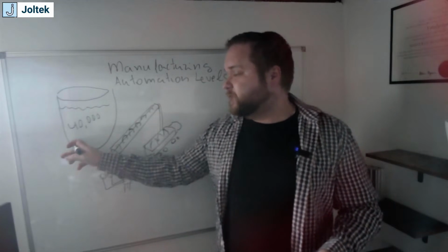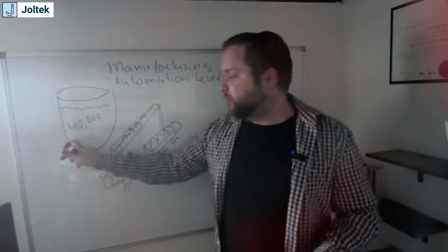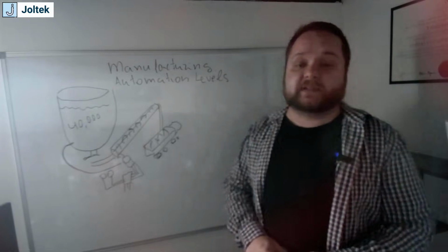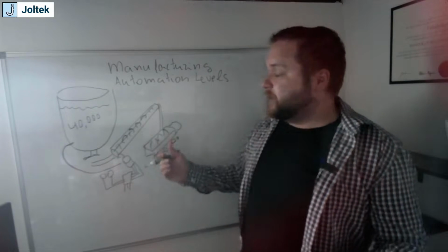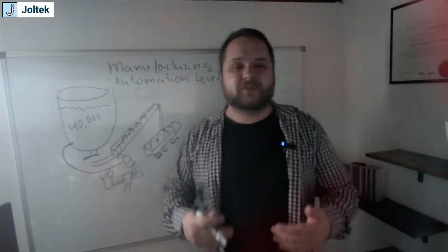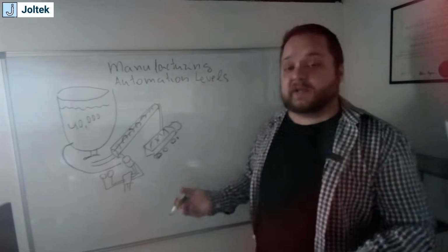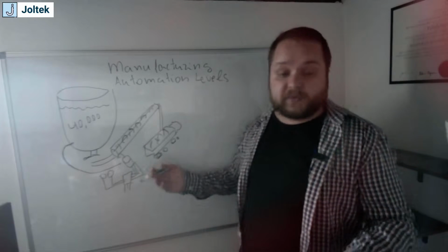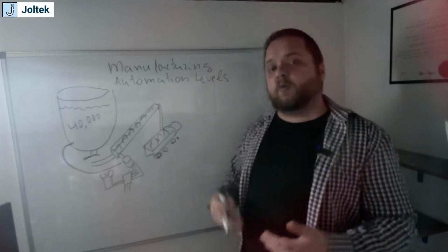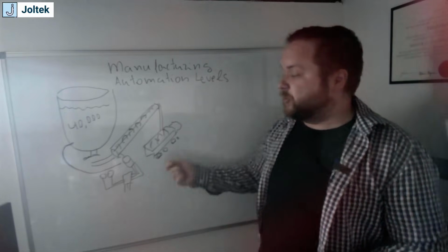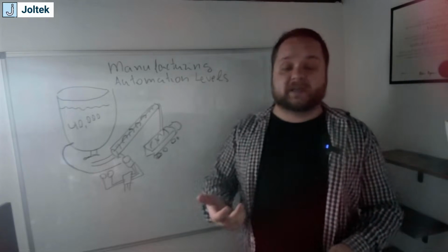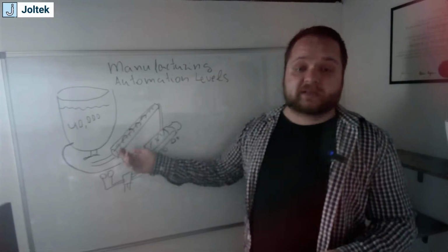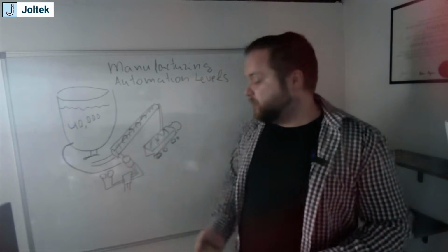So again, there are going to be different VFDs that can be set up where you have a sensor that's going to stop a specific tank at a certain point in time, but really you don't have a controller, so there's no way to notify somebody if an issue has occurred. And if there is a problem, for example the VFD throws a specific error, then it's going to take a while to respond. So unless you have some kind of a notification system that will send you a message on your phone or any kind of device, you're not going to know that the system has failed. So it may take some time before you can repair.